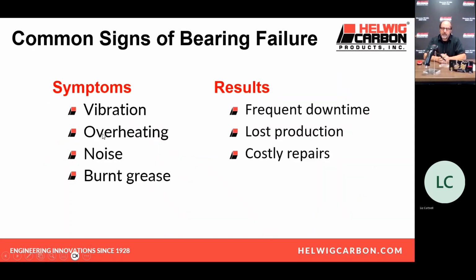How do you know you've got a bearing failure? What makes you recognize your motor as having common signs of premature bearing failure or bearing failure at all? The first thing you want to do is look for vibration in the motor. The roller elements of the motor are running over a rough surface due to deterioration, and the motor shaft begins to vibrate, and it's felt throughout the motor. The motor will be getting hot. You can literally hear the vibrations when you get near the motor. And one of the first things you should look for is if you have burnt grease, not grease that's dark in color, but actually burnt black grease. The net result of bearing failures: downtime, production, and costly repairs.